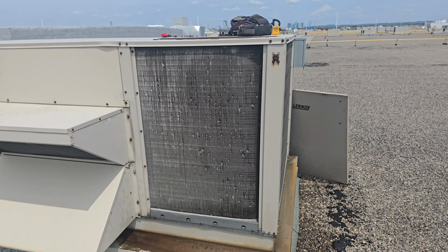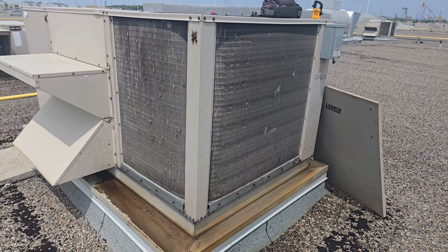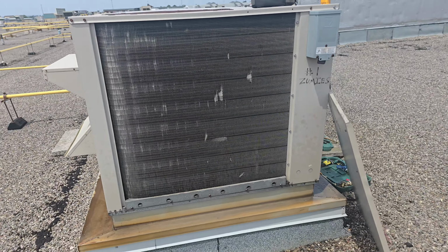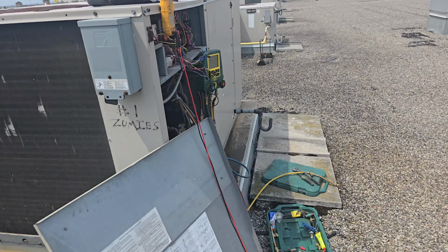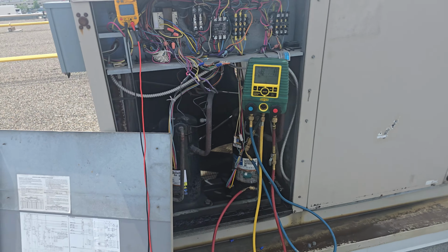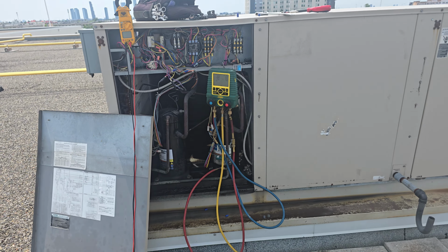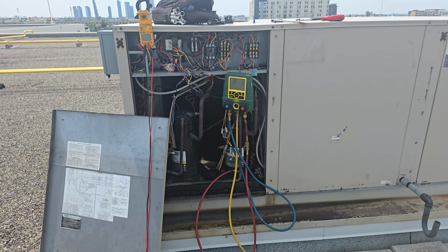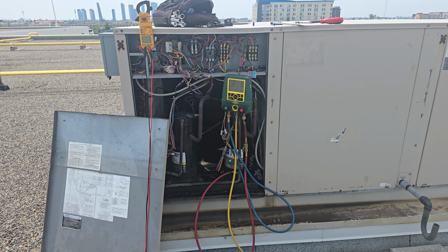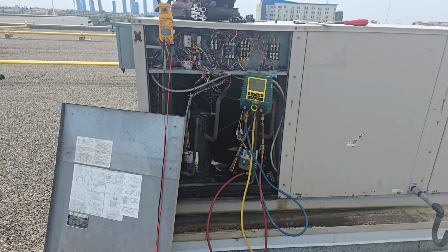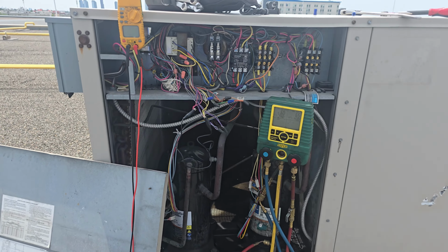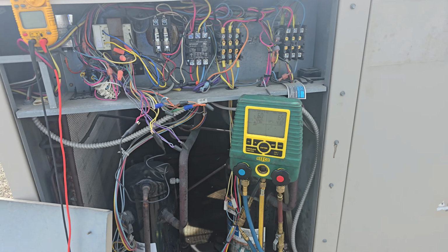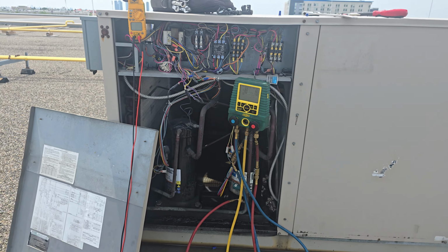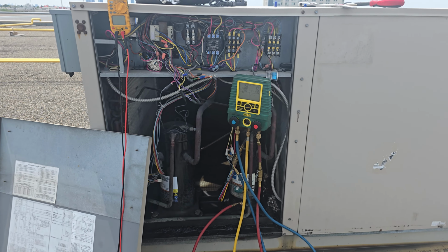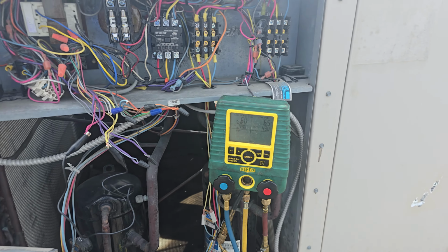And again, I'm going to put about 60 psi of nitrogen into the system, pressurize it, and then use a soap test or a leak test to find the leak. And if that leak is found, then we will braze it. If it's not on the condenser, it could be in the evaporator. So I'm going to do that.